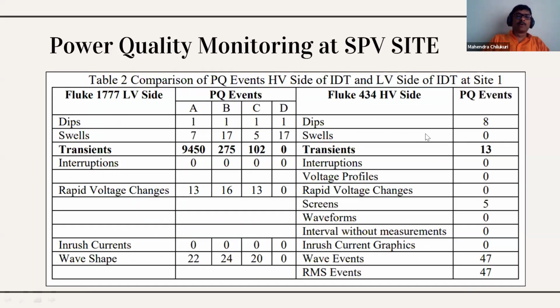If you look at this table, out of all the power quality events, the report only identified 13 transients as exceeding the limit. But otherwise, the transients are around 9,000 on one phase, 200 on B phase, and 102 on C phase. When one particular phase has so many transients, definitely something is bound to happen in that phase, because it is not happening evenly on all phases. But if you look only at the power quality report, you will only see something small.